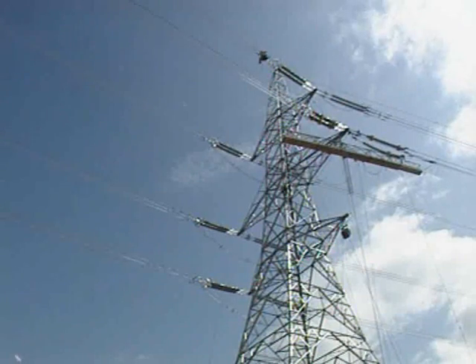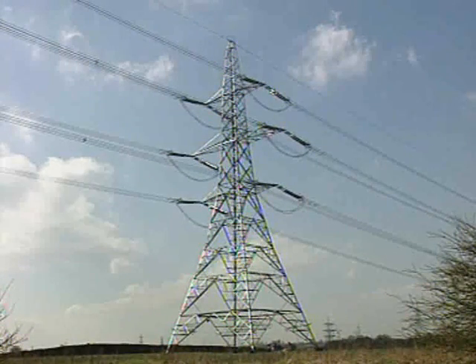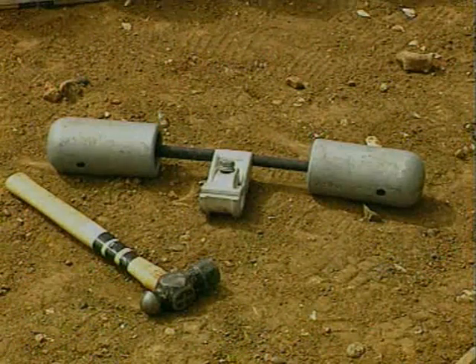Connections between the sections of the line are made by means of bow-shaped conductors called jumpers. To prevent these long lines from building up oscillations in very high winds, devices known as stockbridge dampers are fitted near to each insulator.